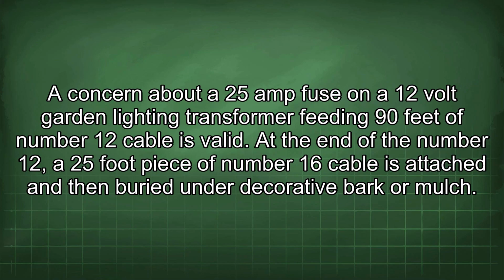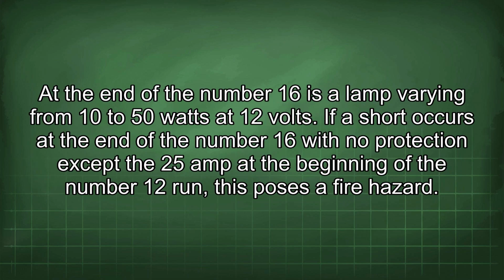Concern about a 25 amp fuse on a 12 volt garden lighting transformer feeding 90 feet of number 12 cable is valid. At the end of the number 12, a 25-foot piece of number 16 cable is attached and then buried under decorative bark or mulch. At the end of the number 16 is a lamp varying from 10 to 50 watts at 12 volts. If a short occurs at the end of the number 16 with no protection except the 25 amp at the beginning of the number 12 run, this poses a fire hazard.